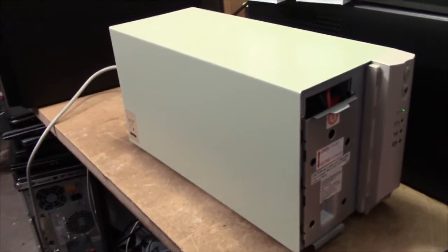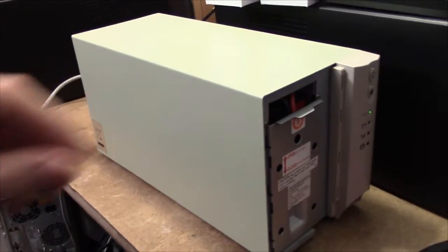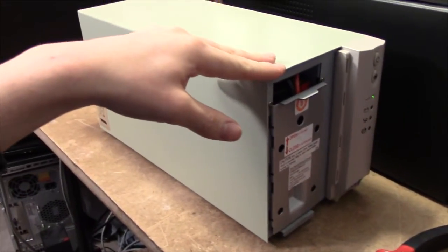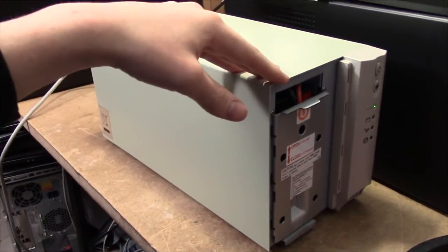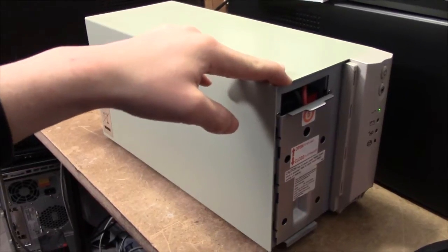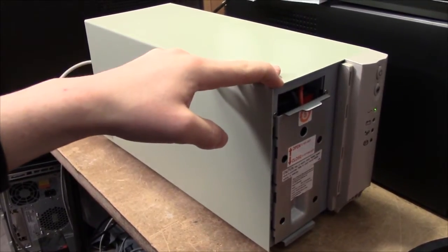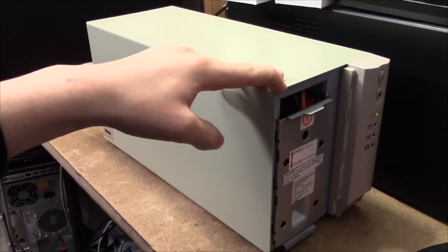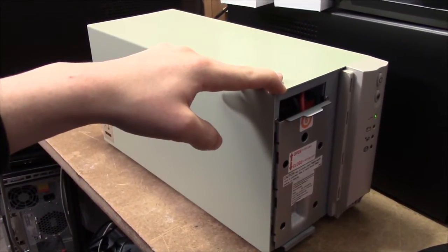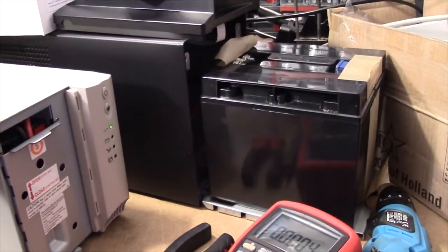Aside from that, these are excellent units. They are not transformer based. They are entirely switch mode. And they've got either two or three state charging off the batteries, which is a lot more than the equivalent APC units have.